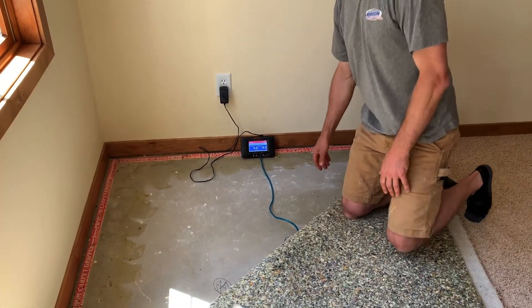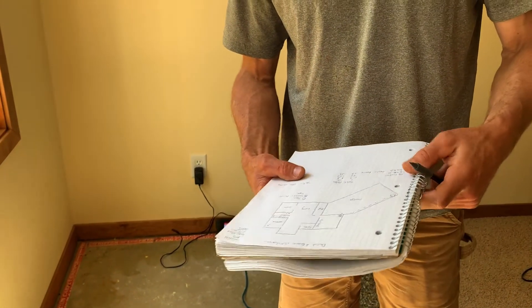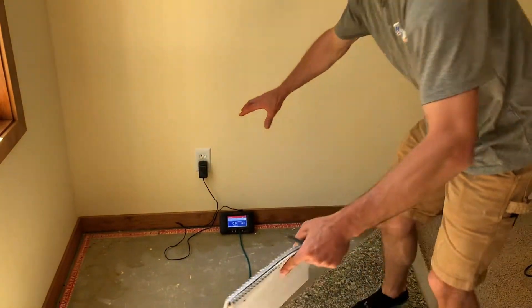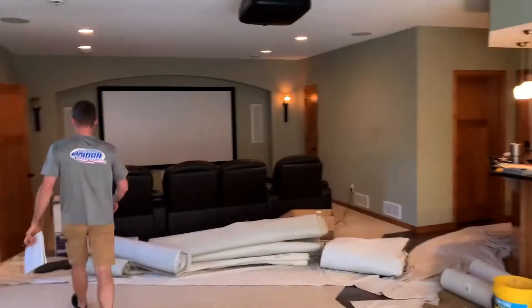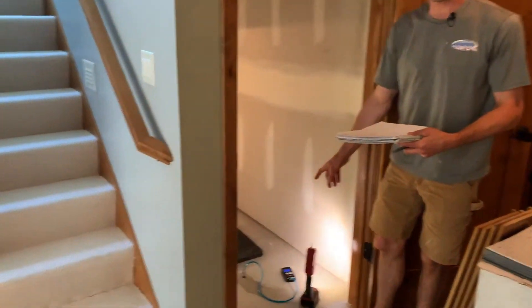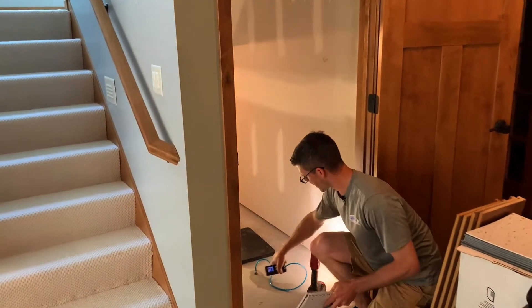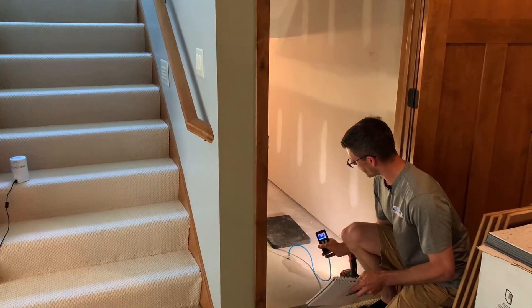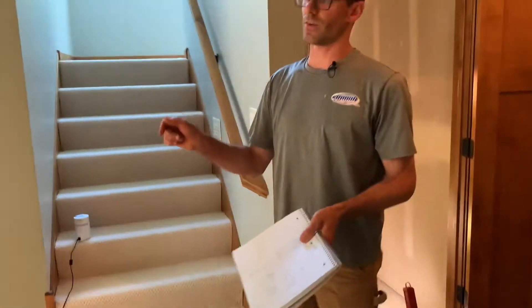We located here and drilled our test hole with no suction. This one was reading positive 0.7, meaning the house was sucking air right in. We've got another test hole back under the stairs here, which was reading positive 0.2, so we had more soil gas entry over there than here. Currently we're reading about 22–23 pascals negative on this one and negative 9 over on that other one.